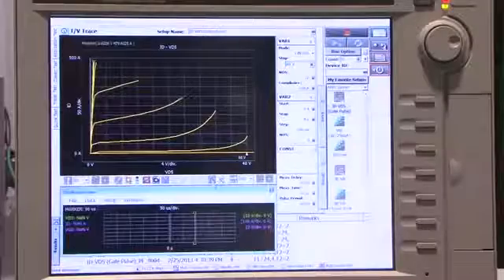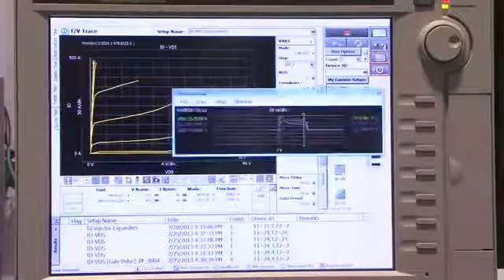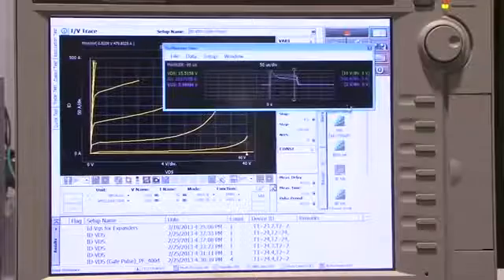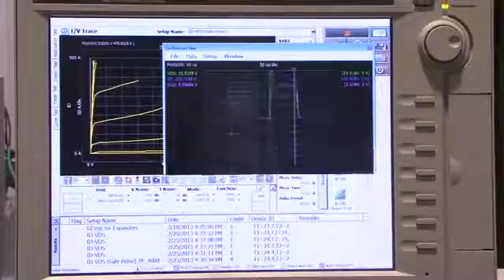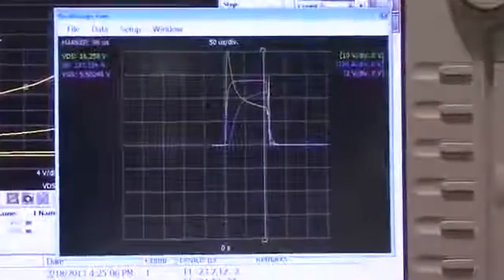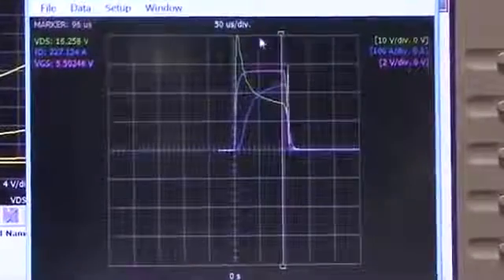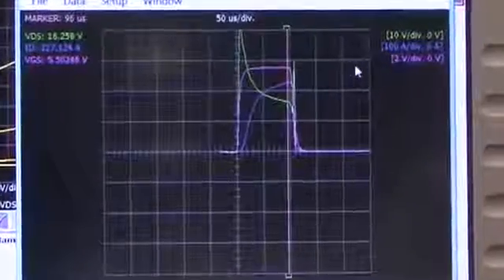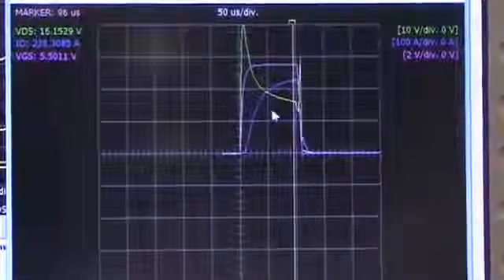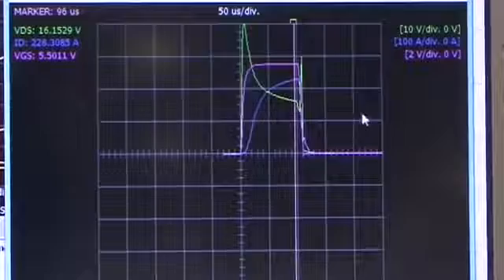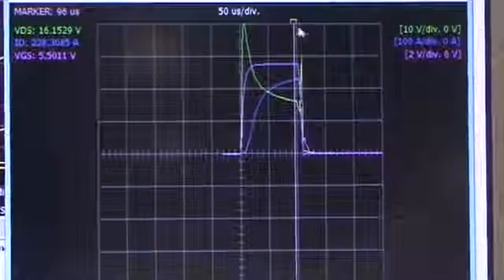It has a lot of really nice features including an oscilloscope view which actually allows you to go in and look at the waveforms as you're pulsing the device. You can actually verify waveforms, for example, right on the box without using a separate oscilloscope.